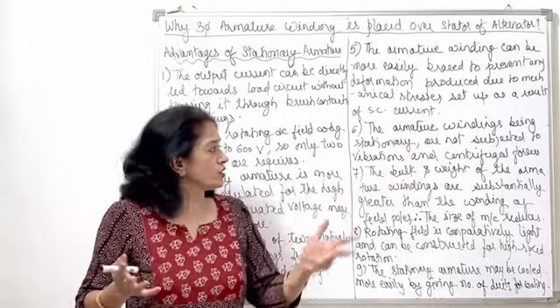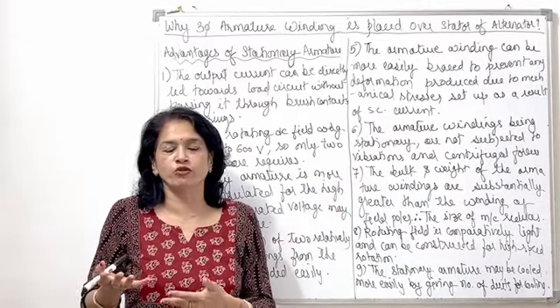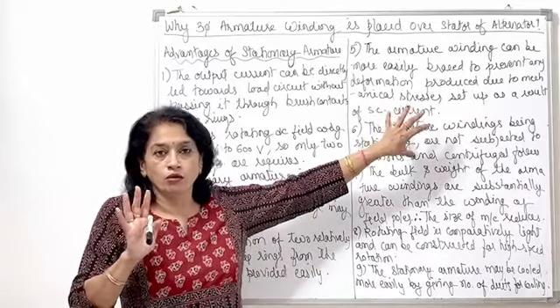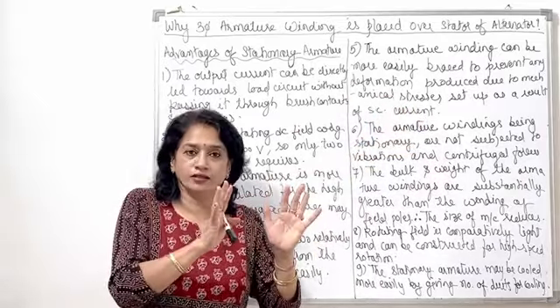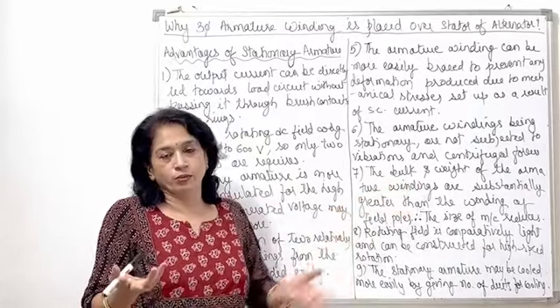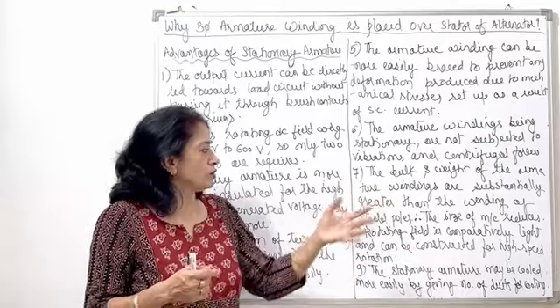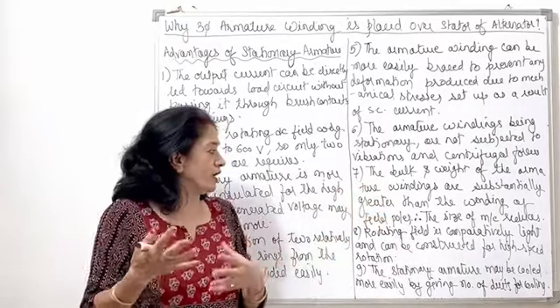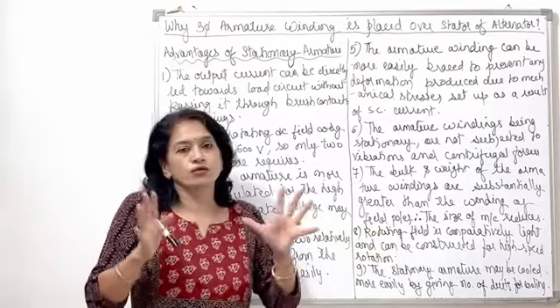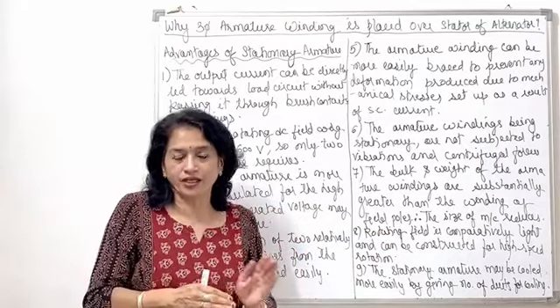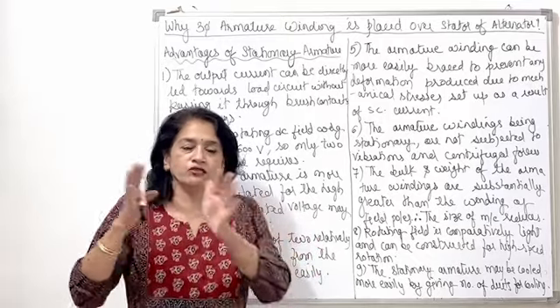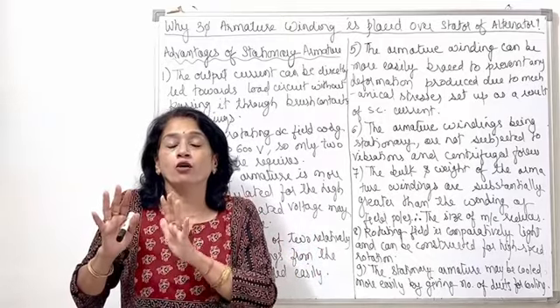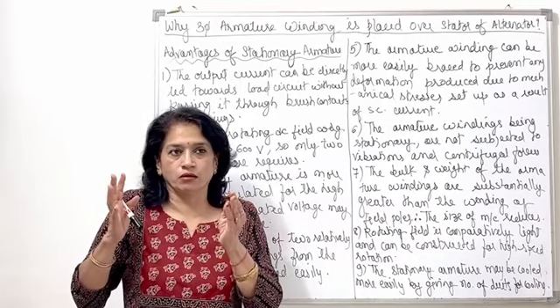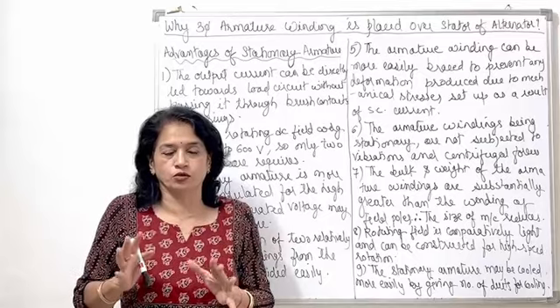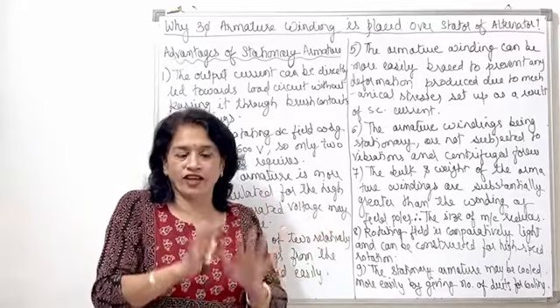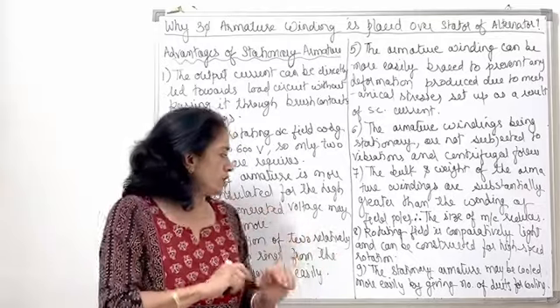The armature winding is stationary and not subjected to vibrations and centrifugal forces, so it is quite easy to have a large bulky armature winding as a stationary circuit. As I said, it is bulky and its weight is very high, substantially greater than the winding of the field poles or the DC field winding. If the three-phase armature high voltage winding were provided over the rotor, it would create a big weight as well as a more bulky structure. So it is easy to reduce the weight and bulkiness by having the armature winding over the stator.